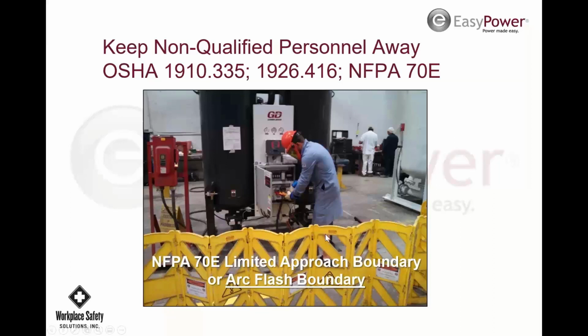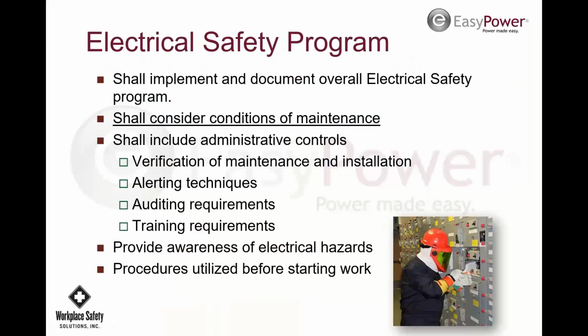Now this barricade is out there quite a distance, so I would not say that this was out there for any arc flash boundary distance. This is a control cabinet with probably quite low level stuff. So the shield may or may not be needed. It may be just part of their policy that they use it all the time. So the electrical program in the NFPA standard says we should implement and document an overall electrical safety program.